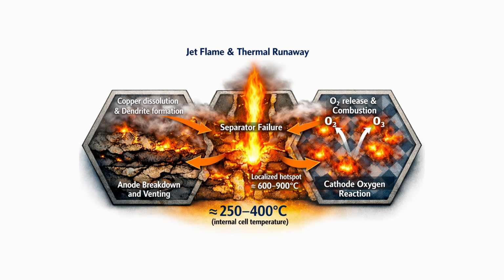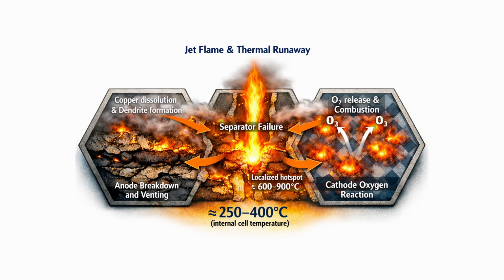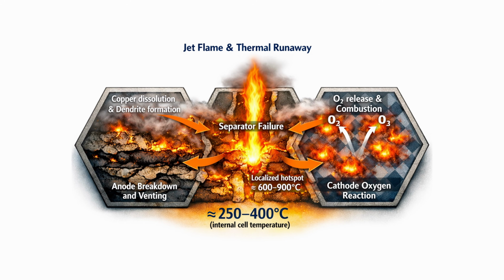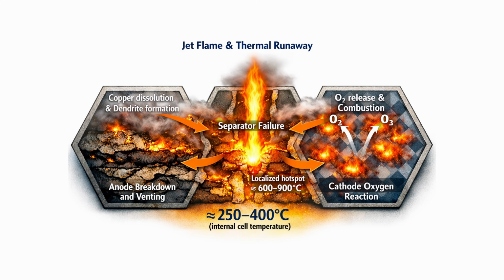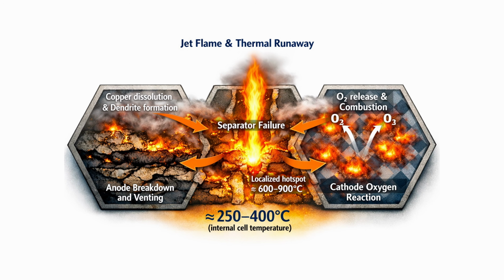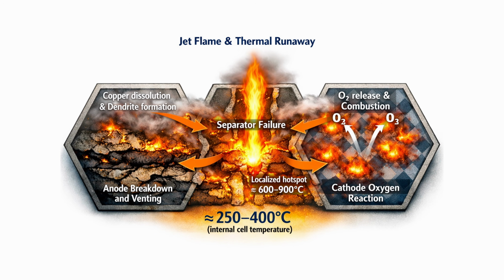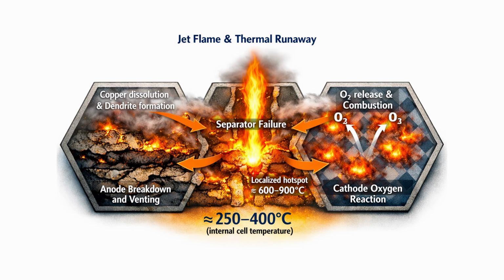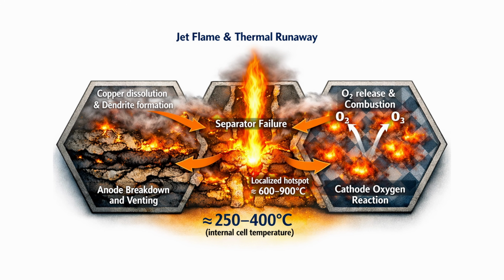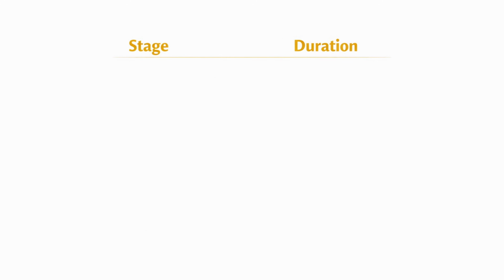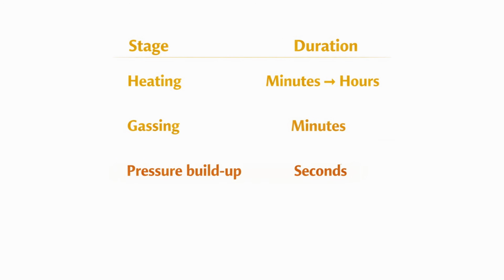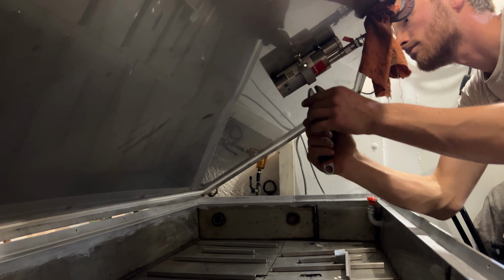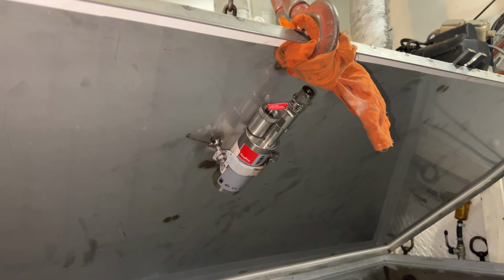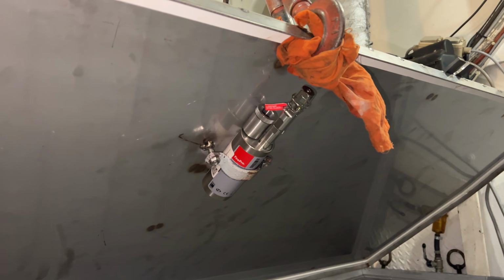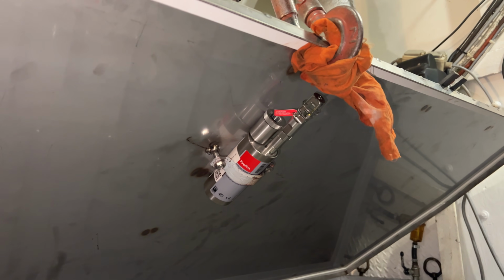The fourth stage is the actual thermal runaway event, the short jet flame. Inside the cell, temperature can reach several hundred degrees and the cell vents a hot burning jet for 1 to 5 seconds. This is the dramatic part you see in online videos. But it's important to understand that it only happens after all the earlier stages. First heating, then gas, then pressure, and only then the jet flame. And because the FirePro has already filled the enclosure with aerosol, flames cannot form outside of the module. So even during this stage, the heat stays contained inside the battery box.